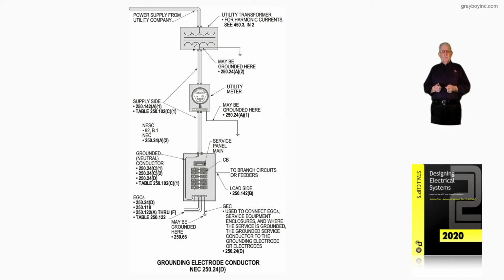Now this illustration deals with the grounding electrode conductor. Many times, people say, well, exactly what does the grounding electrode conductor do for you? Well, you have to go to 250.4(A)(1) to really look at that grounding electrode conductor and what it performs for you. And basically, you know what it does. It diverts lightning strikes, surges. It regulates the voltage to ground, that kind of thing. But all that's identified in 250.4(A)(1).